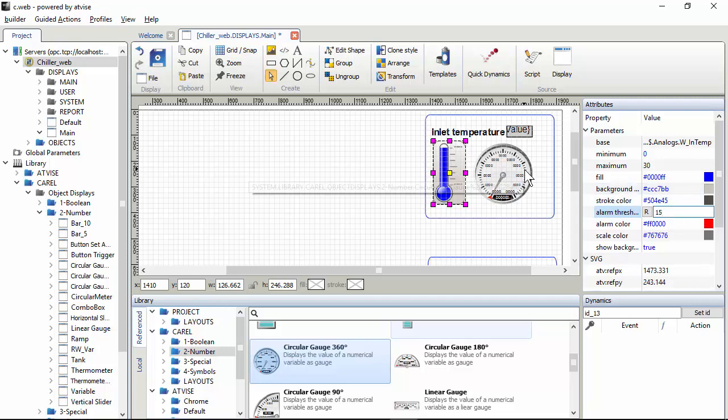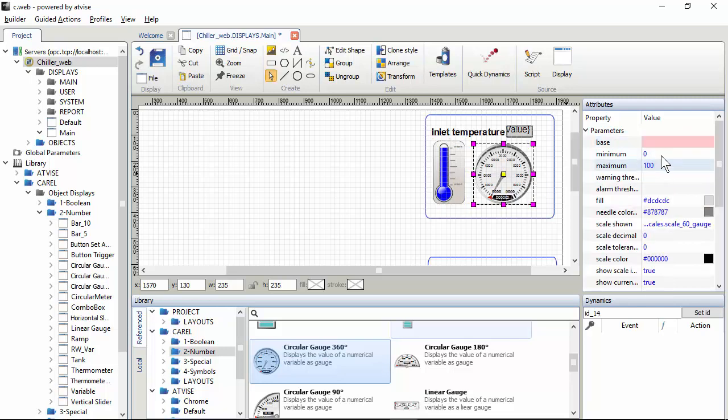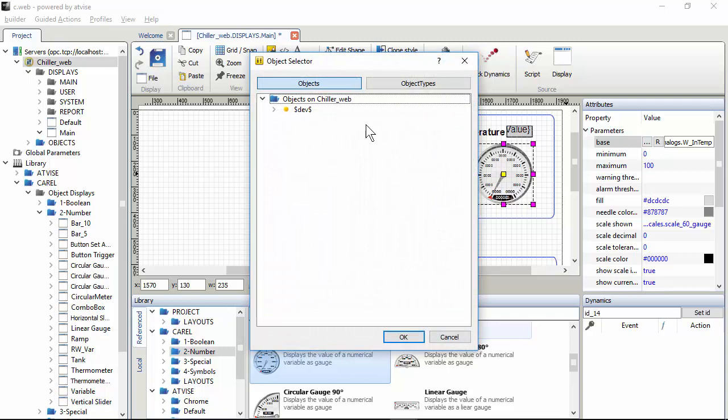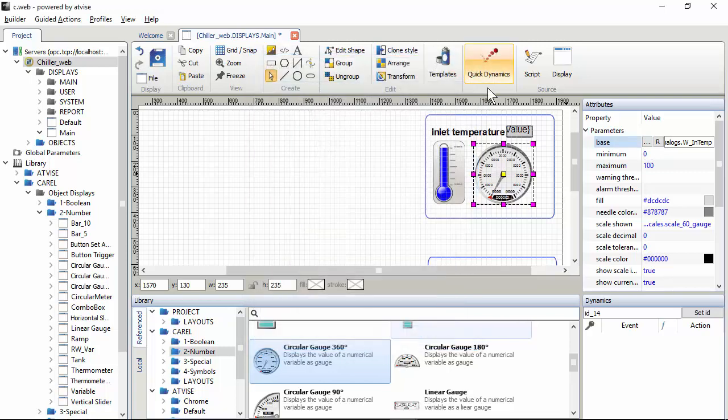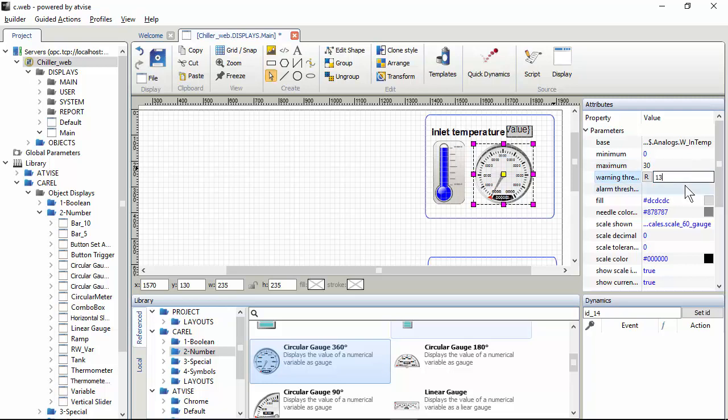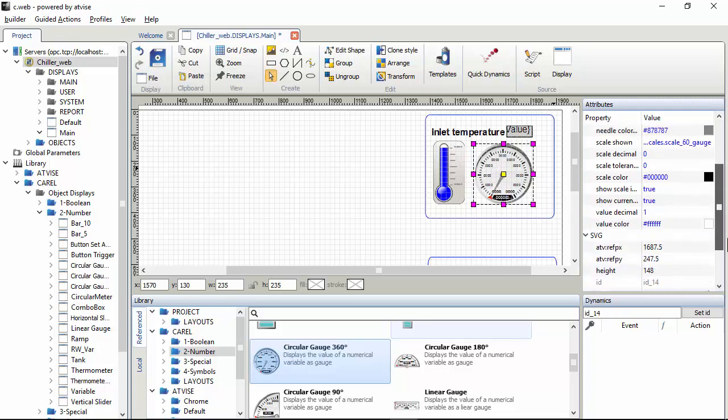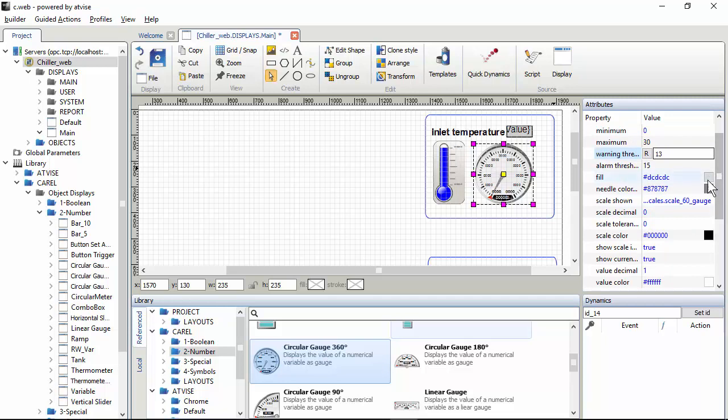Also this one. For this one, you can copy this name, click and paste here. So you can type directly the name as well as select from here. Also for this, we can set the limit to 0 to 30. This has two limits: warning and alarms. So the warning could start at 13, the alarm at 15. At 13 degrees, the needles become yellow. And if I remember well, we can set from this property yellow and in the alarm change to red. Okay, that's enough for this.